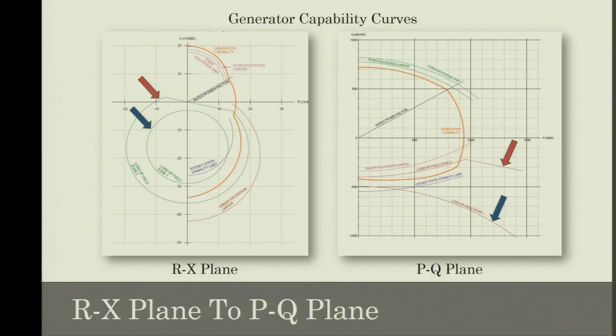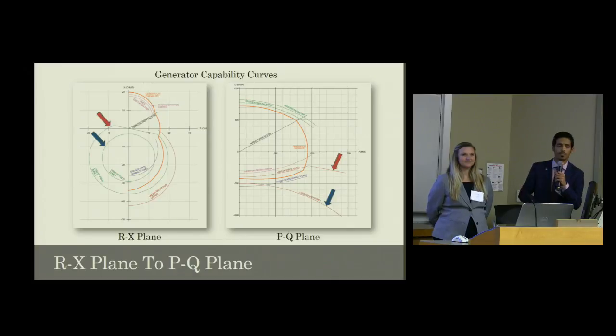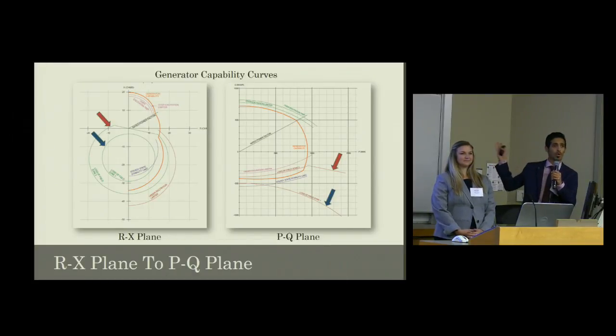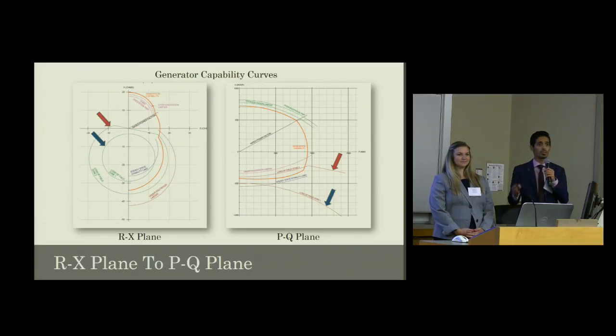Those are in the RX plane, and we can see that they are just two simple circles. However, when we did the conversion to the PQ plane, the shape is different, and we can see that as the two curves in the bottom of the PQ plane. We have to point out that coordination can be done on both of the planes, whether the RX or the PQ. However, since Chelan County PUD specifically asked us to implement it in the PQ plane, we had to do the conversion.